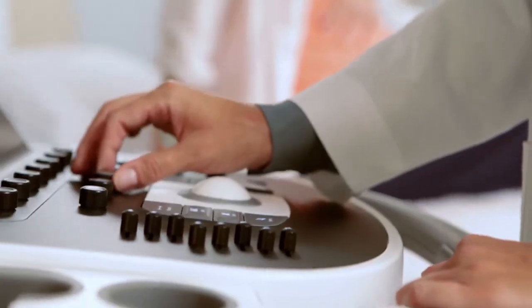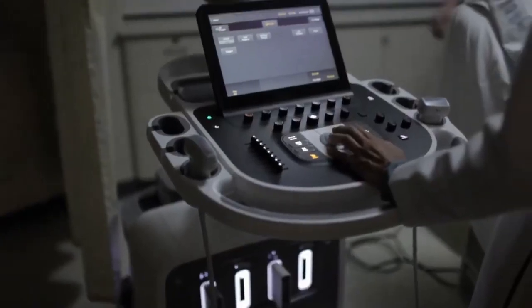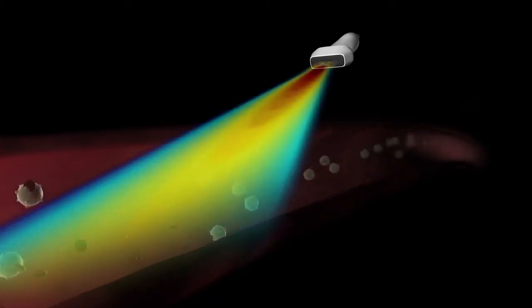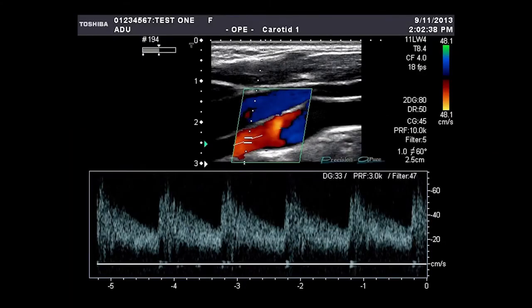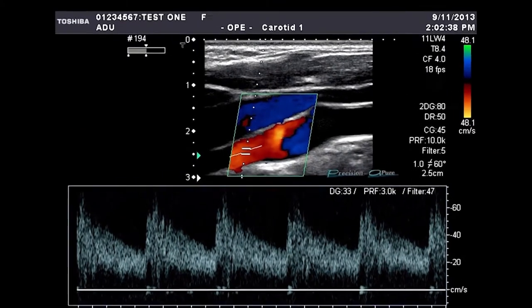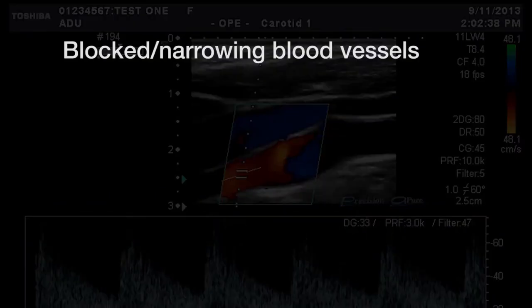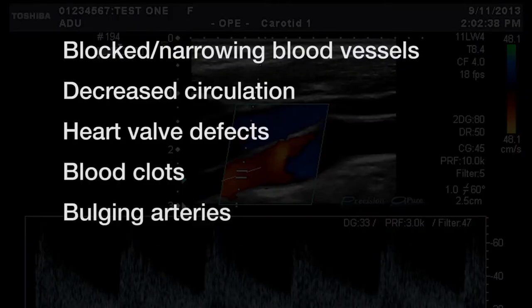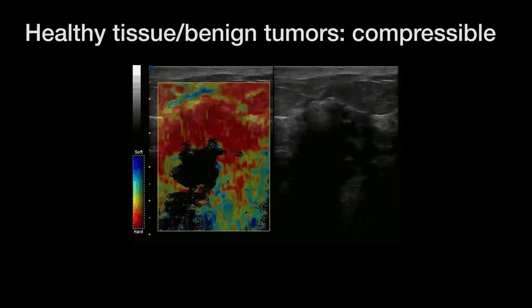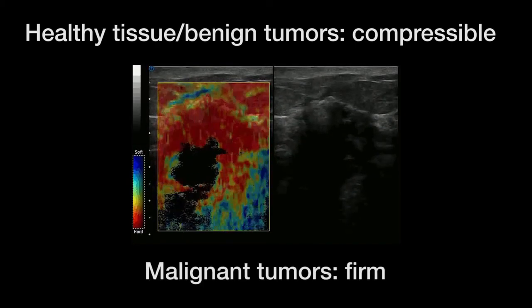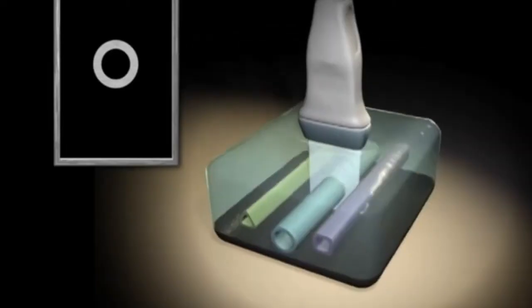First, let's know about types of scanning done in ultrasound imaging. The most common scan used for abdominal studies is the linear scan. A linear scan is when the ultrasonic transducer remains parallel to the surface of the object being examined, and the sound beam is perpendicular to the transducer movement. Only the location of the transducer is changed, but the angle of the beam is held constant. The most common scan used in echocardiography is the sector scan.